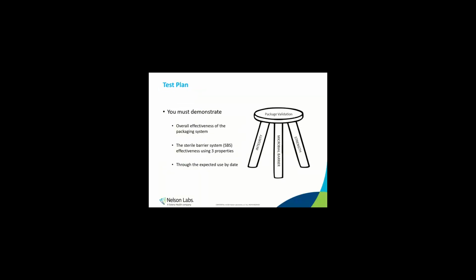There is no single packaging test that can definitively say that a package is good. So we look at 3 different aspects that together give us a more accurate picture of the package performance. These are strength, integrity, and microbial barrier. My 3-legged stool pictured here would be wobbly if one of the legs was missing. Likewise, the packaging validation is not as solid without the multi-property evaluation. I also like to compare it to triangulating a position using GPS. One point gives you a wide radius or a general idea of your location. A second point narrows that location down, but a third point can pinpoint with far greater accuracy your exact location.